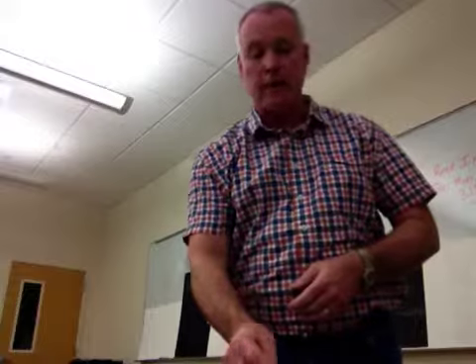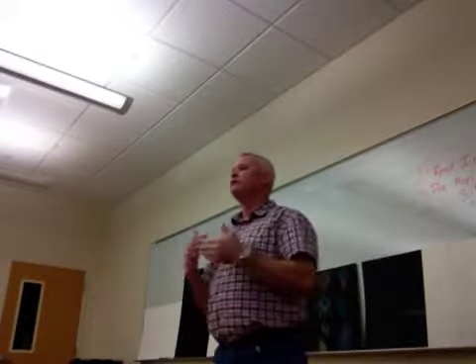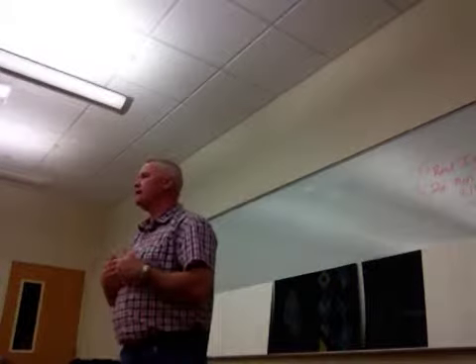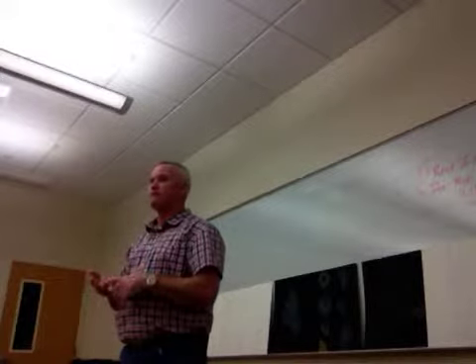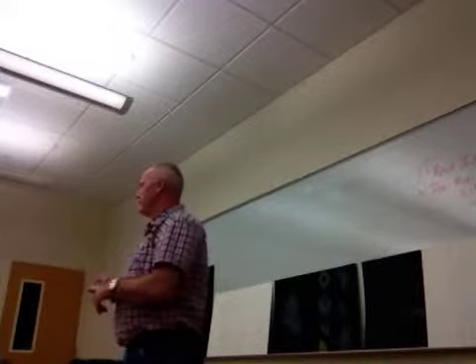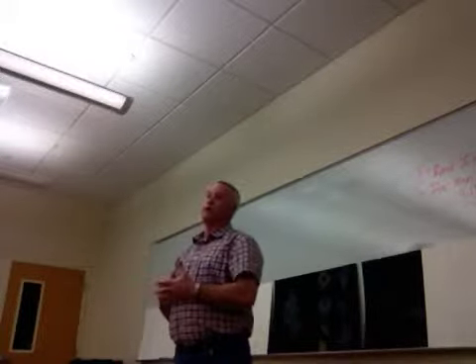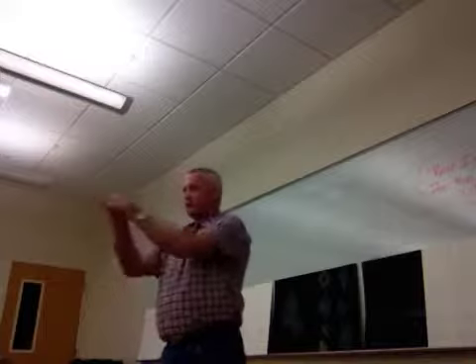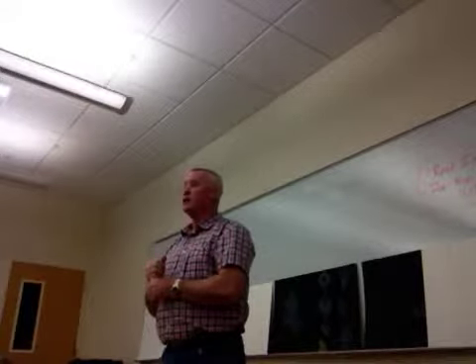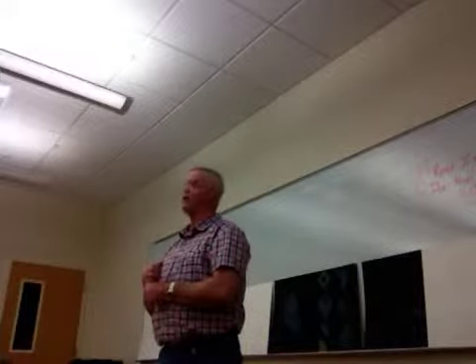Okay, so we talked about AIC. Every switchgear that you specify, or that I specify, has an AIC rating. And we're talking 22,000 amps, 35,000, 65,000, 100,000. That rating tells me that if you have a fault, and when I say fault, think short. There's a short somewhere. Two wires came together that should not come together, and massive amounts of current flow. Well, if that panel board is not rated for that current, it'll blow off the wall, literally blow off the wall and kill somebody, or catch the place on fire, or all the above.